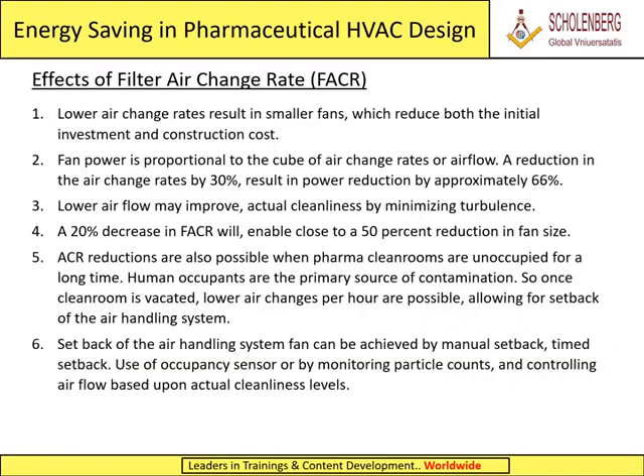Effects of filter air change rate, FACR. 1. Lower air change rates result in smaller fans, which reduce both the initial investment and construction cost. 2. Fan power is proportional to the cube of air change rates or airflow. A reduction in the air change rates by 30% results in power reduction by approximately 66%. 3. Lower airflow may improve actual cleanliness by minimizing turbulence. 4. A 20% decrease in FACR will enable close to a 50% reduction in fan size.